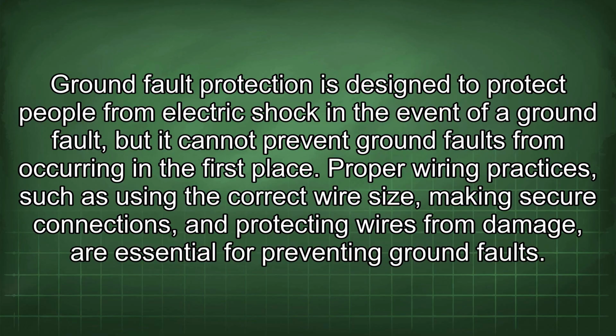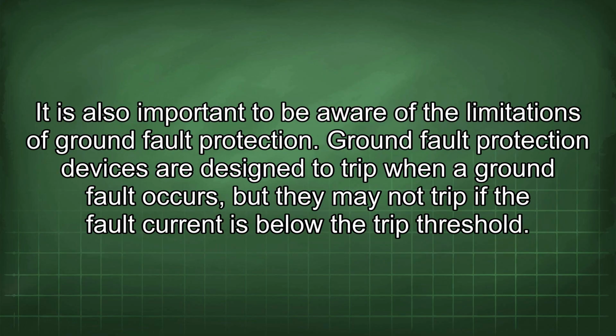Proper wiring practices, such as using the correct wire size, making secure connections, and protecting wires from damage, are essential for preventing ground faults. It is also important to be aware of the limitations of ground fault protection. Ground fault protection devices are designed to trip when a ground fault occurs, but they may not trip if the fault current is below the trip threshold.